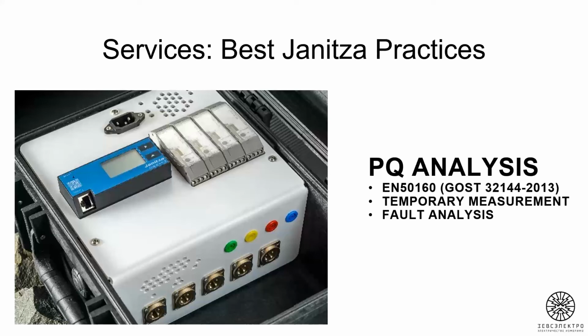We have a new question: do you use transducers as input for gas, air and water to feed into the UMG input, or do you use third-party devices? Well, as you know, UMG 604 has Modbus via RS485 interface or analog temperature input. Not all transducers use such an interface, so we have to use analog transducers which reduce the analog signal to 0 to 10 volts and 4 to 20 milliamps to transfer it, or via Modbus TCP or Modbus RTU interface. But all of the data is collected with GridVis Ultimate. So my answer is: third-party devices we use sometimes.